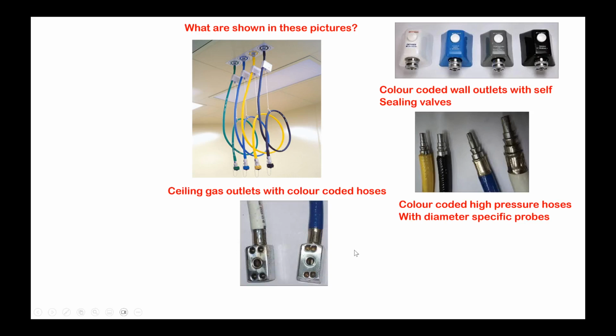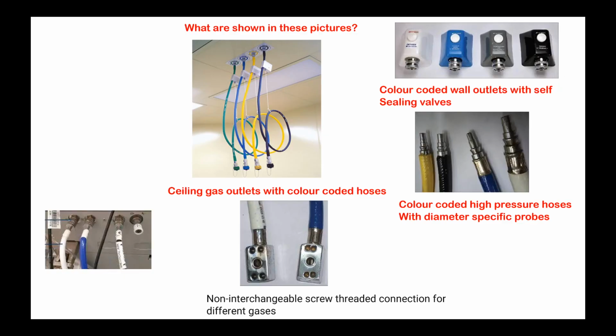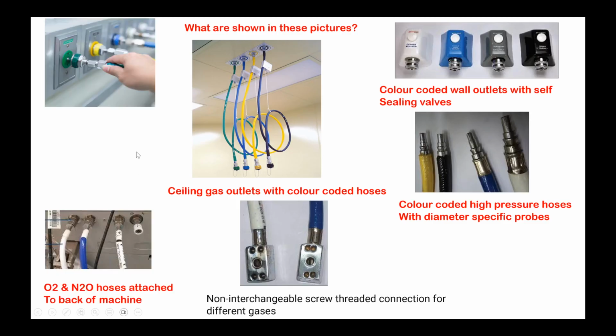What is this? Pin index connection to the machine. Okay, non-interchangeable screw threaded connection for different gases, which is going to the hanger yoke assembly in the machine. And these are the oxygen and nitrous oxide hoses attached to the back of the machine; in the majority of cases, these are wall outlets.